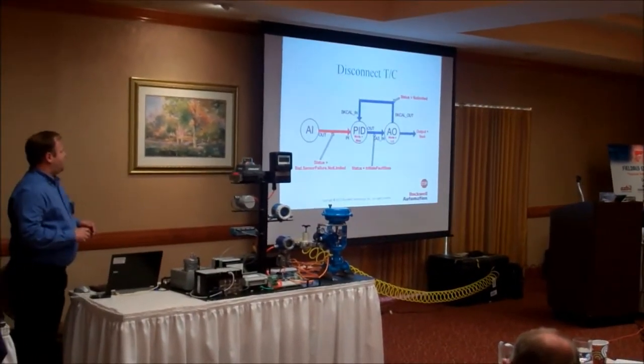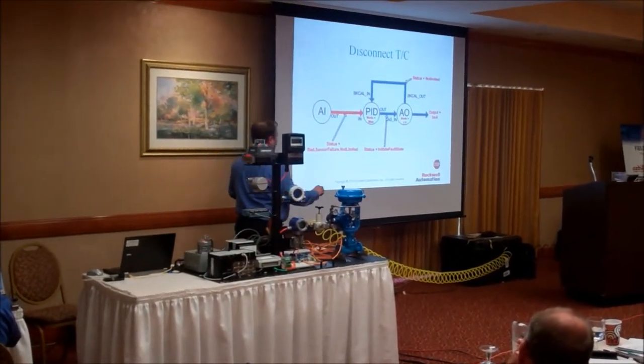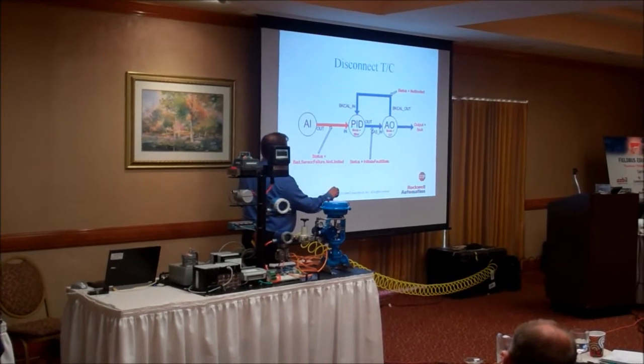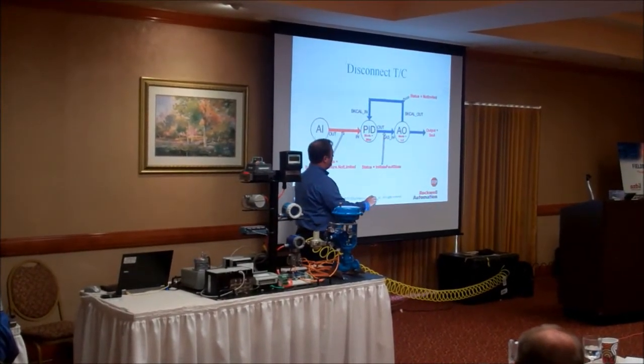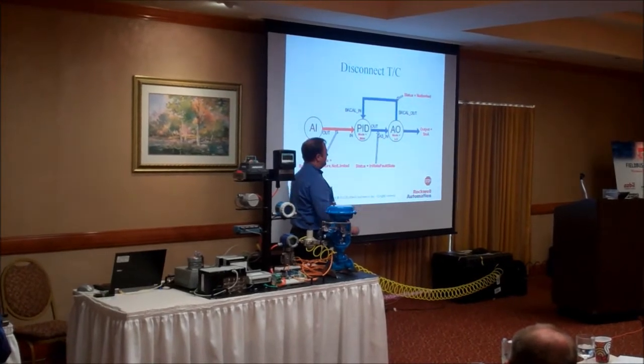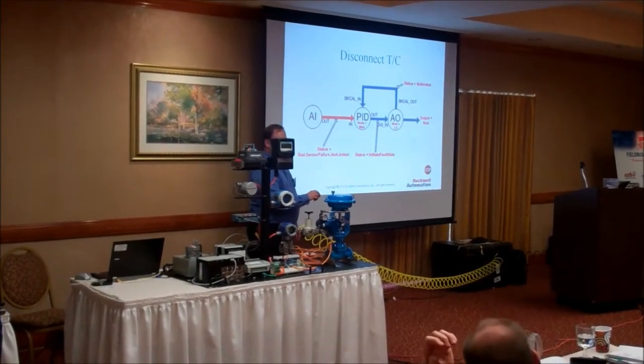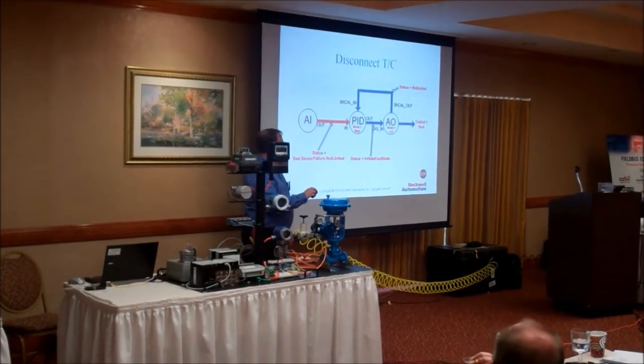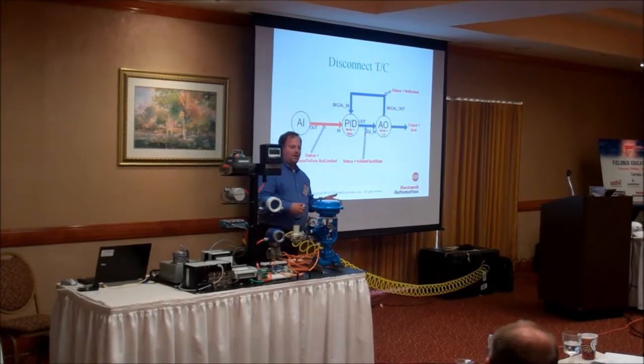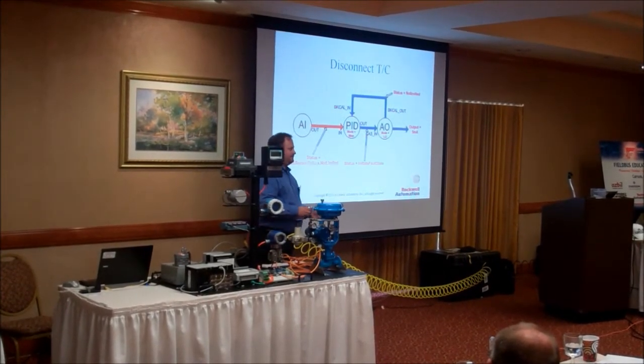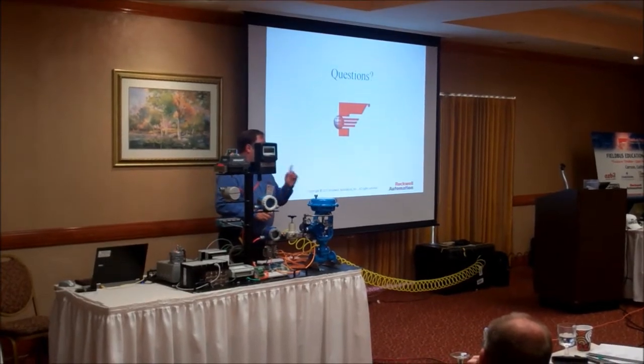Now, if we disconnect the thermocouple here, we're going to see bad sensor failure — not limited. That will propagate into the PID; it will put it into manual, and this will hold the output. You can set it up to go to low output, which is 4 milliamps, or you can set it up to go to high output. But that's all dependent on how you want this to work. The default behavior is last position.